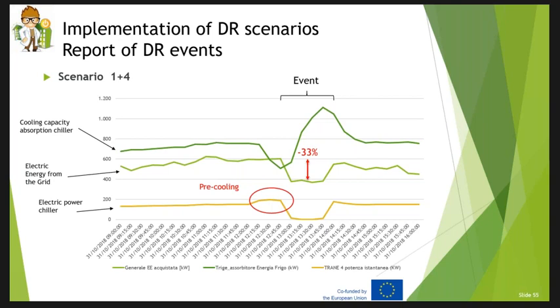So what happened is that, like in the previous event, we pre-cooled the water with the electrical chiller, and during the event we switched the cool production from electrical chillers to absorption chillers. That's why the cooling capacity from the absorption chiller went very high during the event. In this case, we were able to reach minus 33% of the peak power demand from the network.